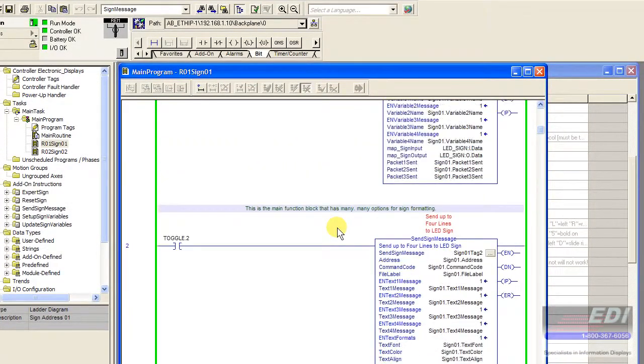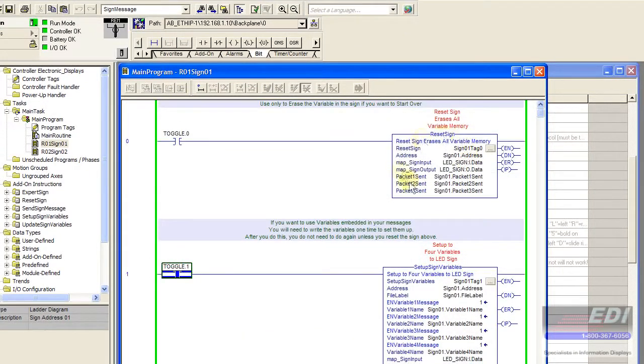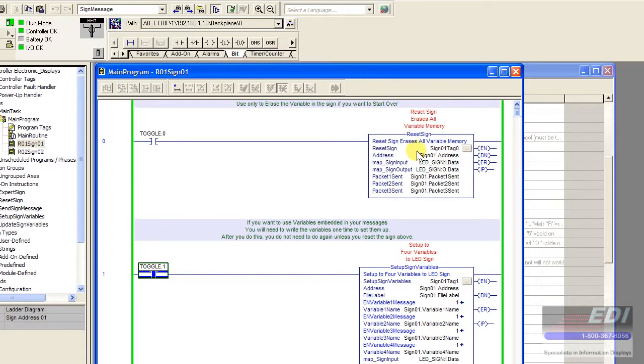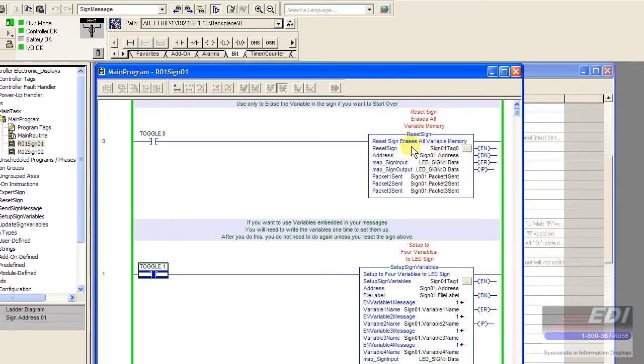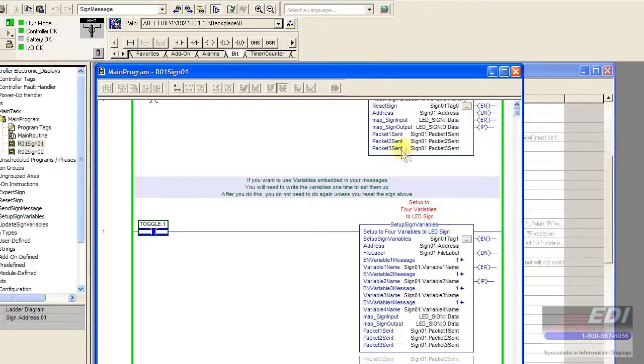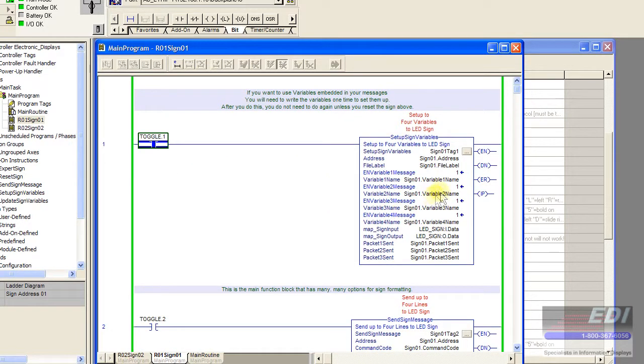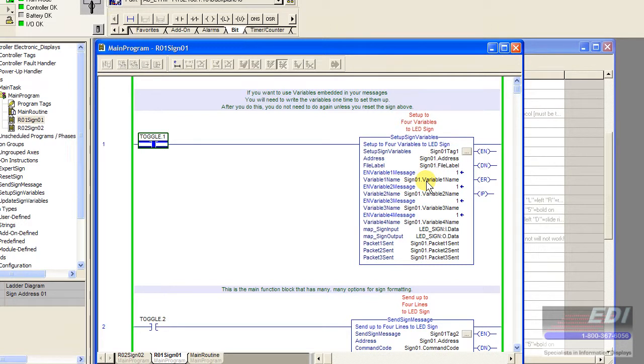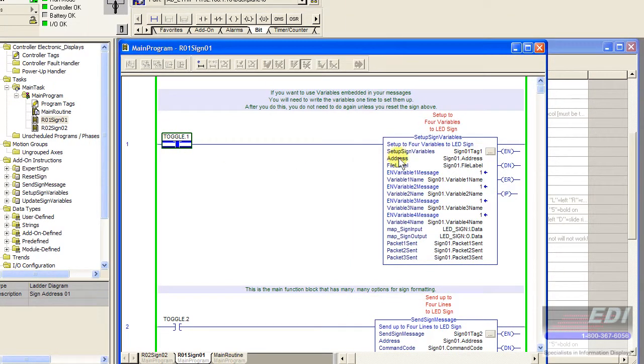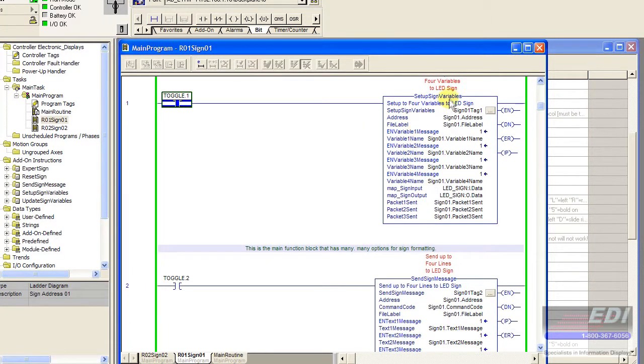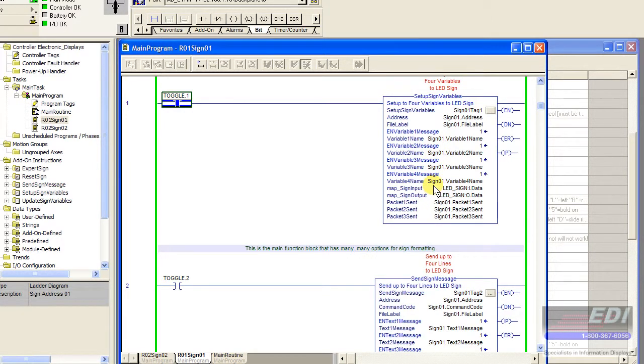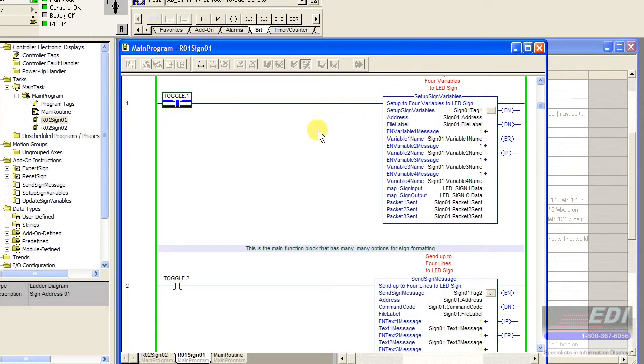This block here is probably a once in a lifetime use. If you need to erase the sign you're only going to use that on a power up or when you first commission the sign. And this is a once in a lifetime block as well. Part of how the sign works is that we need to allocate a name, a variable name, and the size of memory in the sign. This only needs to happen once but your variables will not work until you allocate the variable name and size in the sign memory. Once we've done this one time we're pretty much done with this rung.